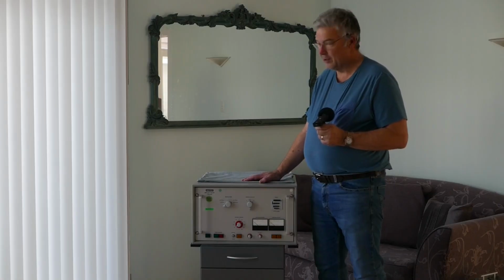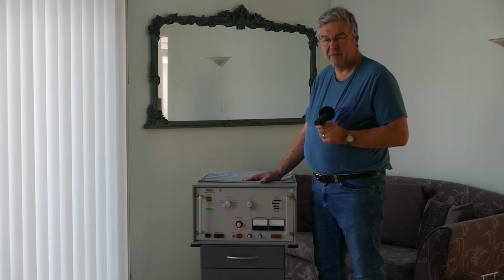Today we get to look inside something a little bit different. This is a 6 kilovolt impulse tester. What does it do? Well, it simulates lightning strikes or grid events that generate transients on the mains power system.